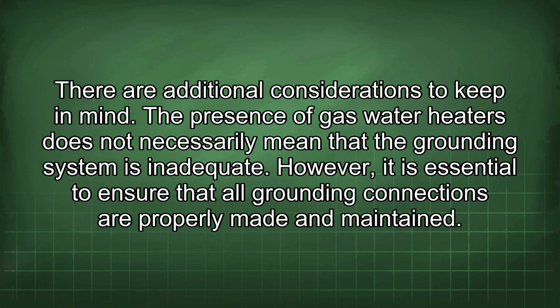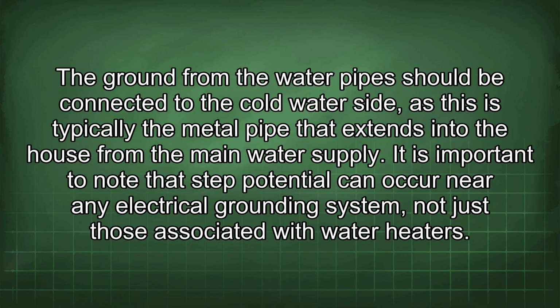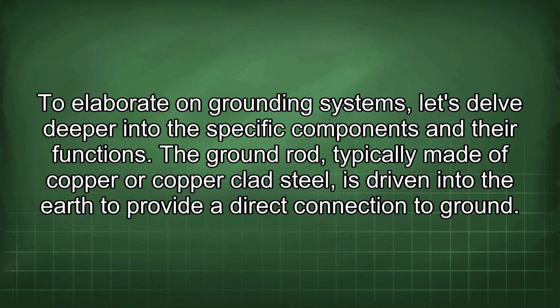There are additional considerations to keep in mind. The presence of gas water heaters does not necessarily mean that the grounding system is inadequate. However, it is essential to ensure that all grounding connections are properly made and maintained. The ground from the water pipe should be connected to the cold water side, as this is typically the metal pipe that extends into the house from the main water supply. It is important to note that step potential can occur near any electrical grounding system, not just those associated with water heaters. To elaborate on grounding systems, let's delve deeper into the specific components and their functions.